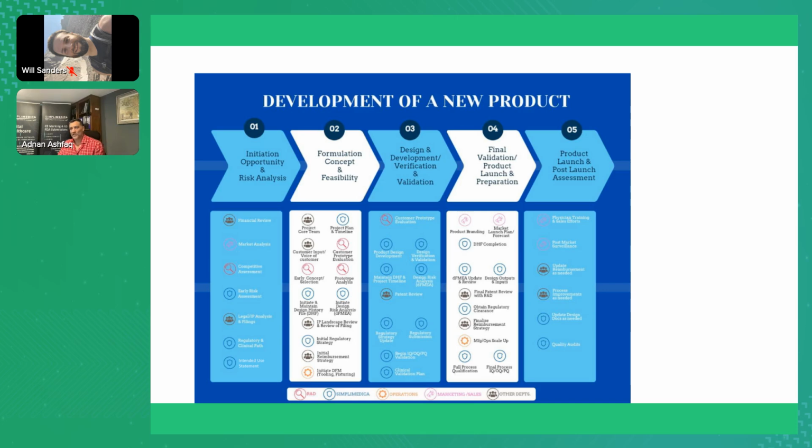It's very important that we understand the intended use starts right at the beginning of the journey, and it's something that we need to keep a check of constantly right through the journey, right through to post-market. And even after post-market, the cycle keeps continuing, because we have to make sure that nothing's changed in the intended use and the intended purpose.